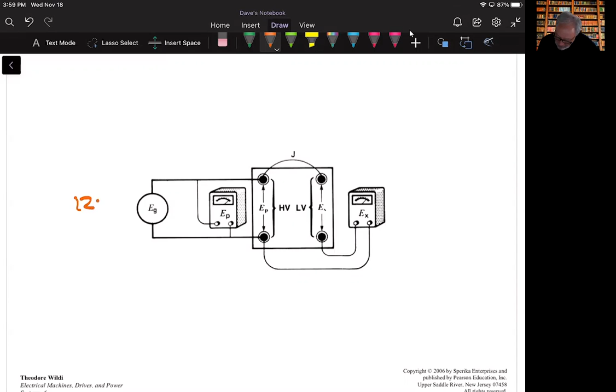To determine whether a transformer has additive or subtractive polarity, this is one method we could use. We start by connecting the high voltage winding to a low voltage source, putting 120 volts AC on the input side here as the source voltage.